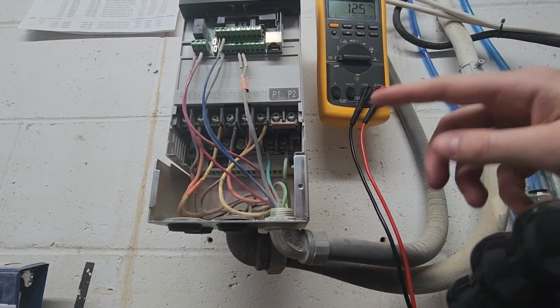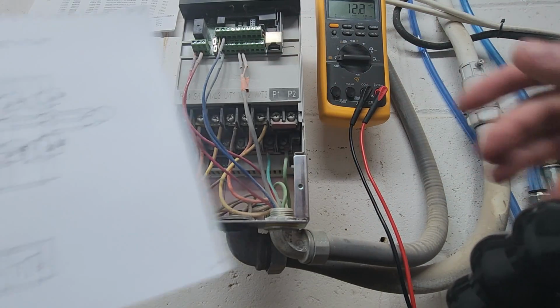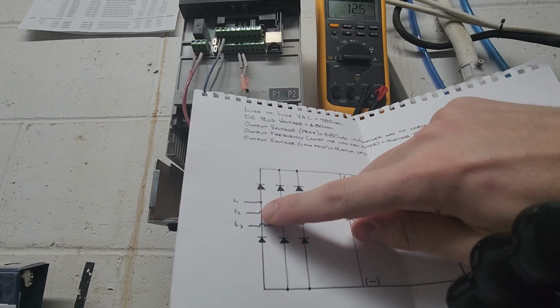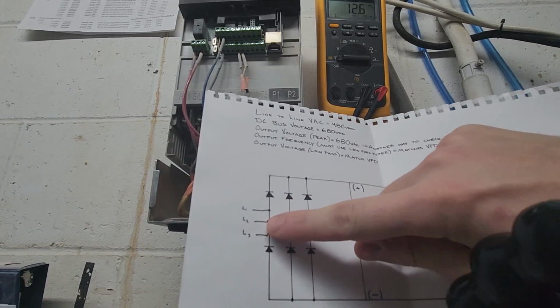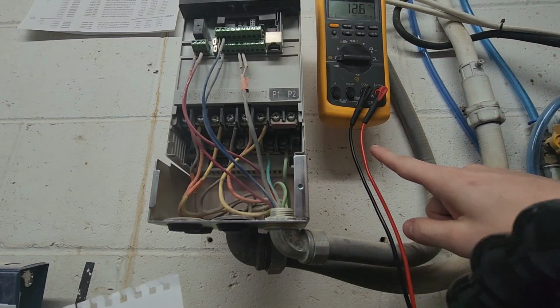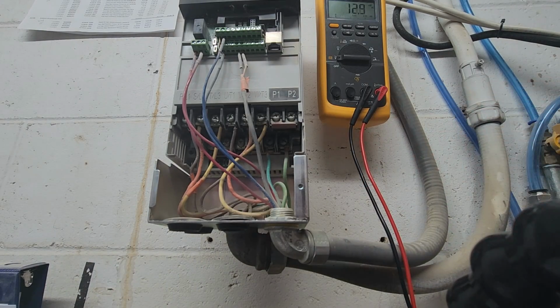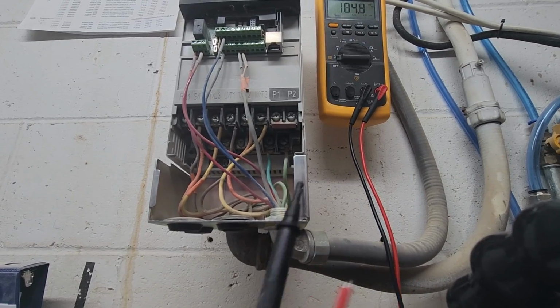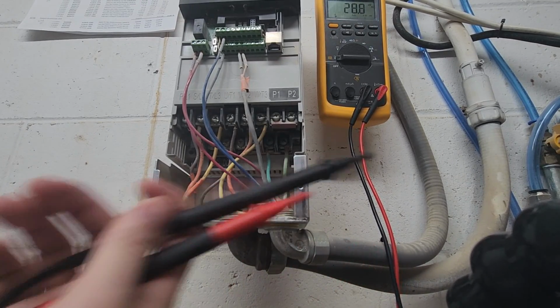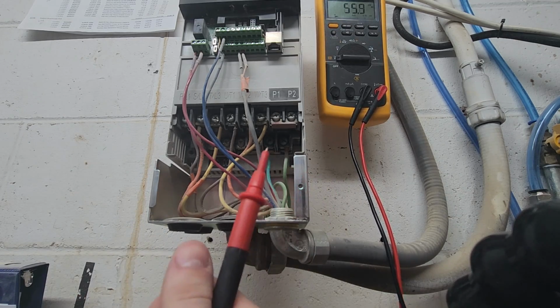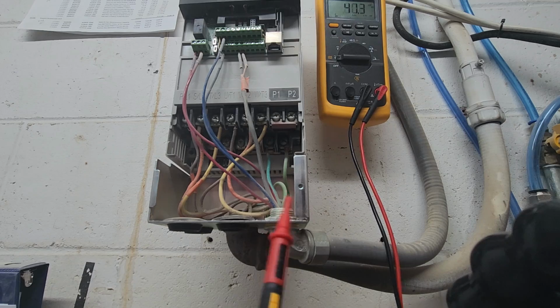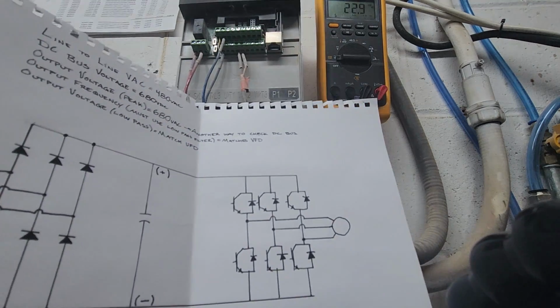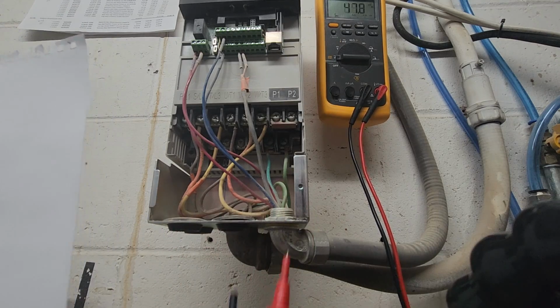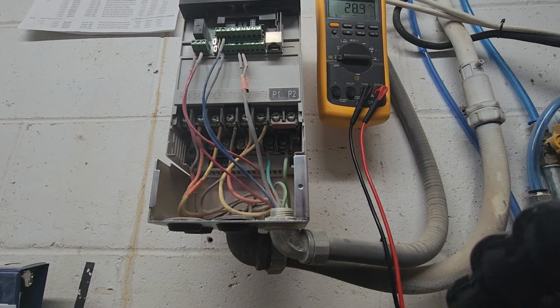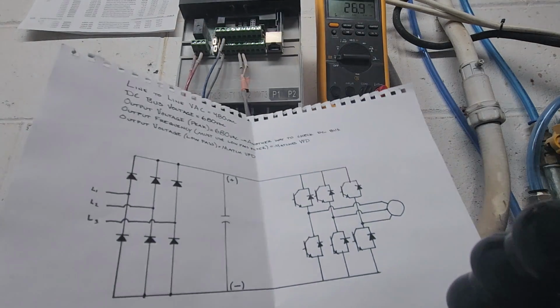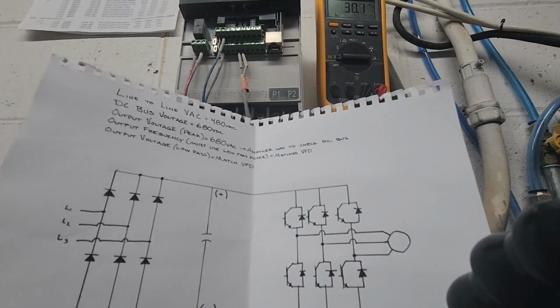All right, I've got power off completely to the VFD, so all the power shut off. Now we're going to test our diodes. So we're going to test these top diodes first. And you got to remember that schematics and your voltmeter use conventional current. So if you study physics, you'll understand that your negative charge actually is the flow of electrons, and then your positive charge is where your electrons are flowing to. But the way multimeters and schematics are, they're in reverse basically. When Benjamin Franklin was flying his kite, he had a 50-50 shot at getting the polarity right on electrons, and he messed up. So here we are, backwards on stuff like this.